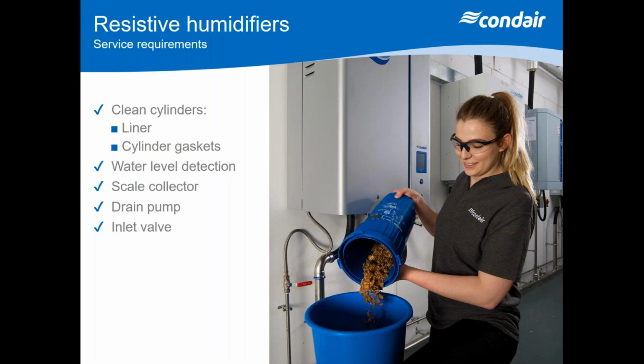It's always worth just checking those switches as part of your maintenance, because if they get stuck, it's going to create issues with the operation of the unit in terms of output, but also with the float operation, it's going to create inconsistent water levels in the tank. The scale collector, as you can see on this one, will be plastic, so there will be a plastics change every so often with these units.